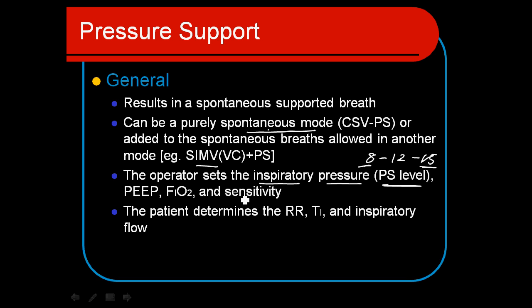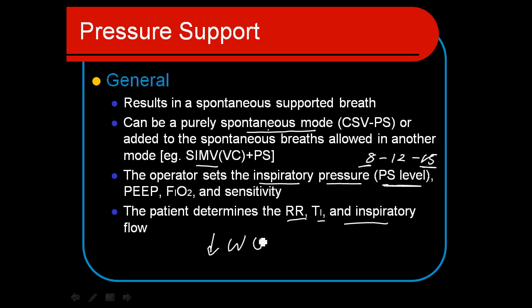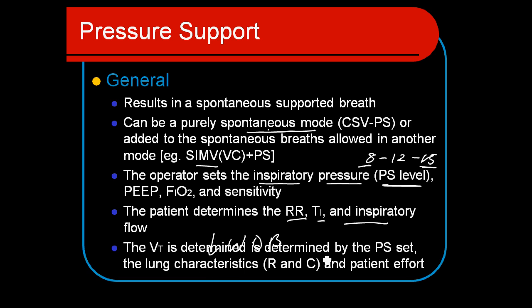We adjust the PEEP, FiO2, and the sensitivity to make sure it's working correctly and meeting the patient's needs. The patient determines their respiratory rate, TI, and inspiratory flow, so they have total control over the breath, but their work of breathing will be decreased dramatically. That's the key element — it decreases the work of breathing, and we control that with the pressure support level set.